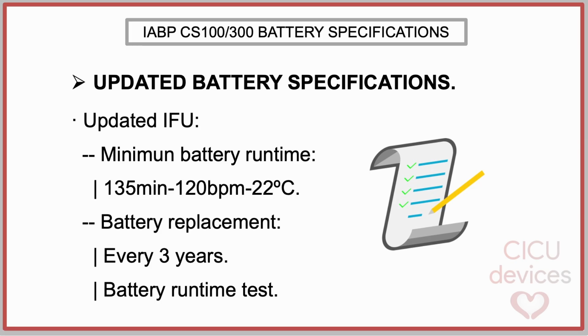Accordingly, the revised instructions for use now define a single minimum battery runtime specification of 135 minutes at 120 beats per minute, at an ambient temperature of approximately 22 degrees Celsius. In addition, the battery replacement guidance has been clarified. Batteries should be replaced every 3 years, or earlier if they fail the battery runtime test during scheduled preventive maintenance.